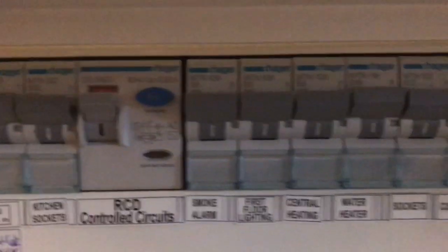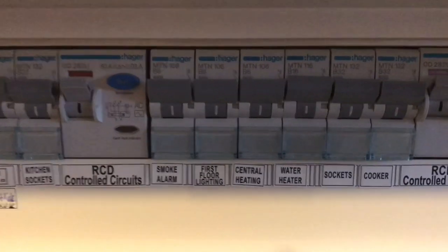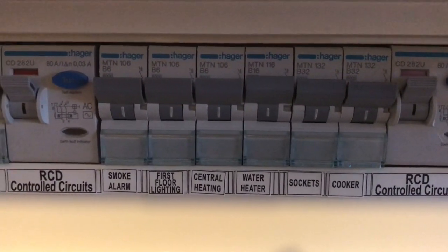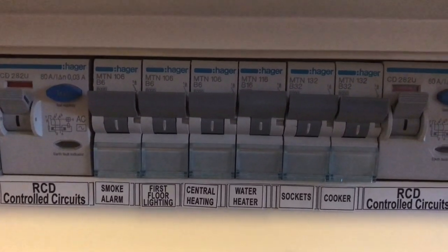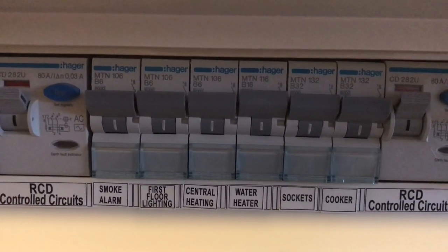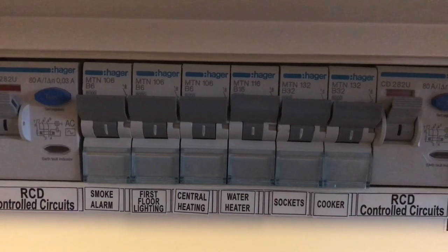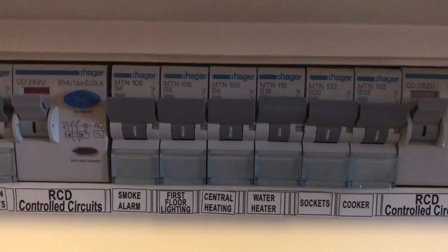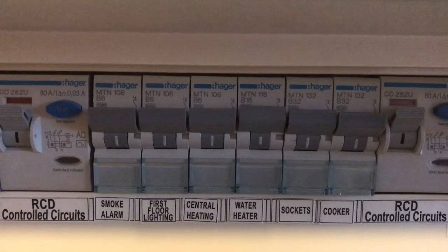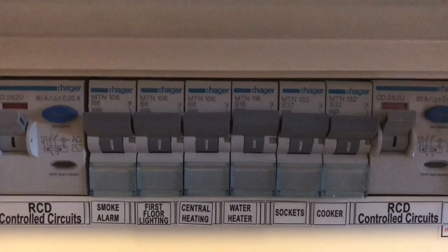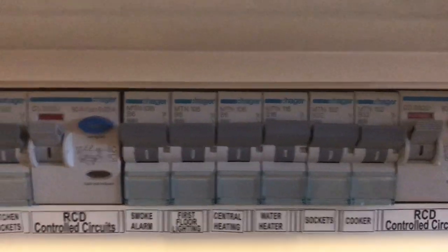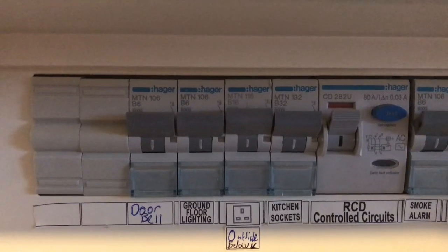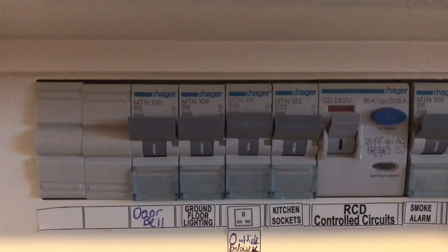And hopefully, if we can see, and we've talked about this before, from the RCD, the circuit breakers are loaded from high to low. So we go from 32 amp to 16, and then our 6s. All B-type, because it is a domestic dwelling with little to no switching surges. And then again, it's a similar loading on the second RCD.